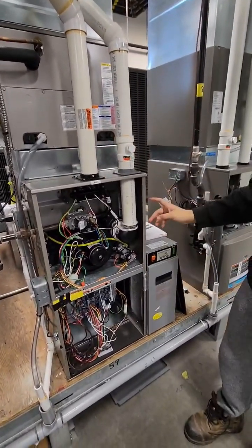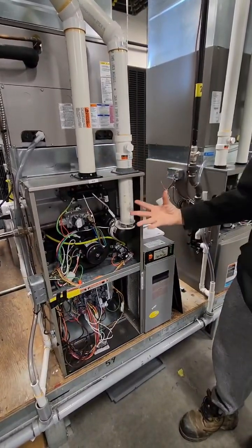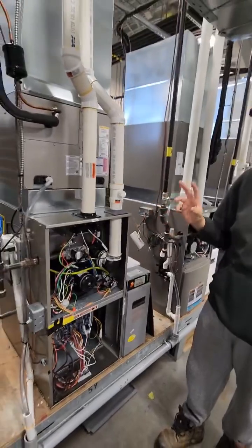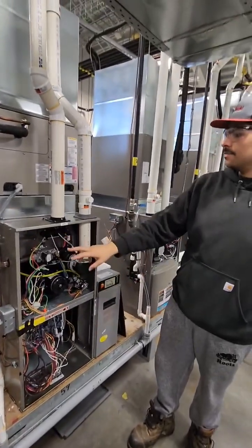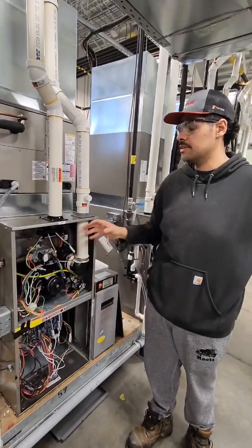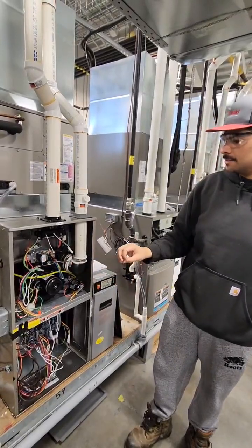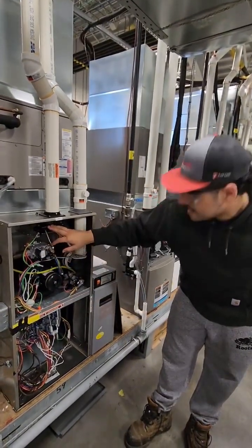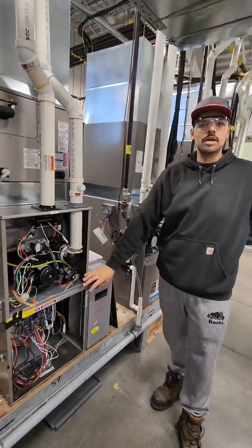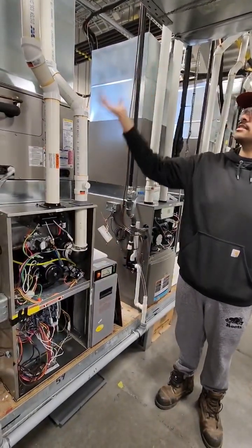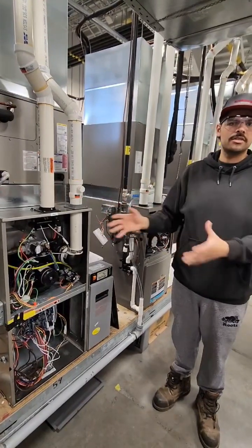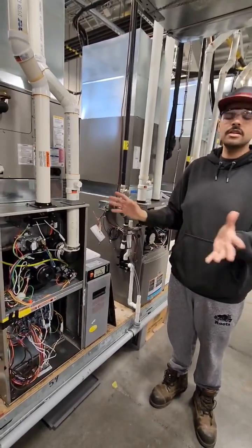After that, you will send power to your HSI, which then will start glowing red. And then after that, once that gets 2200 degrees, that will power your gas valve, which will send fuel through, which will activate the flame to your in-shot burners here. And then after that, your blower motor will come on, and you will get heat starting to come out of your vent.